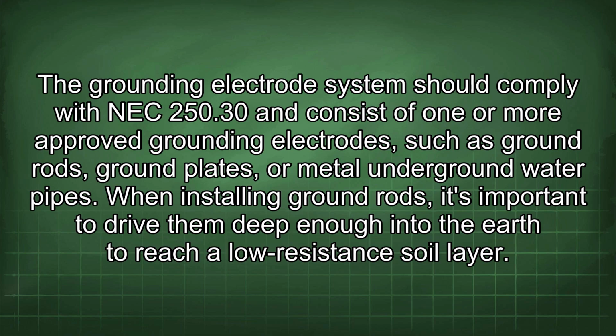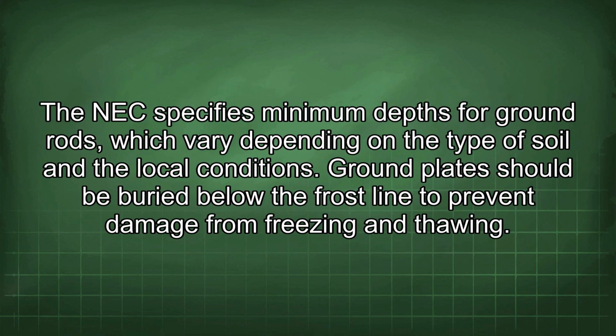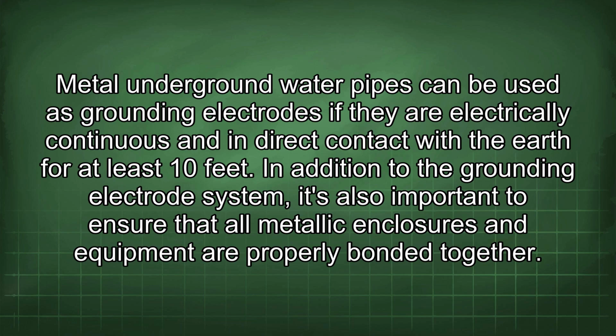When installing ground rods, it's important to drive them deep enough into the earth to reach a low resistance soil layer. The NEC specifies minimum depths for ground rods, which vary depending on the type of soil and the local conditions. Ground plates should be buried below the frost line to prevent damage from freezing and thawing. Metal underground water pipes can be used as grounding electrodes if they are electrically continuous and in direct contact with the earth for at least 10 feet.